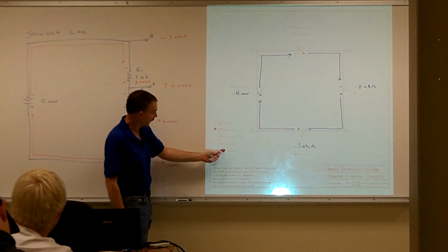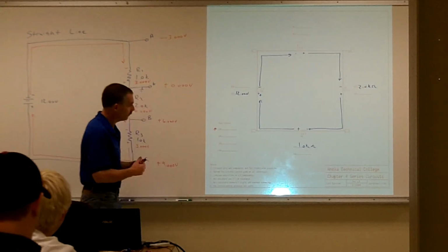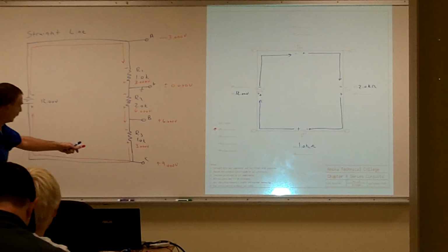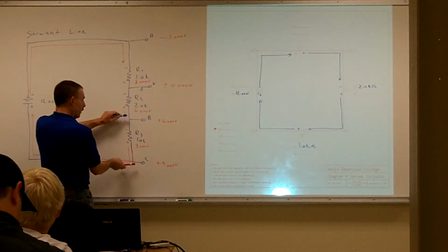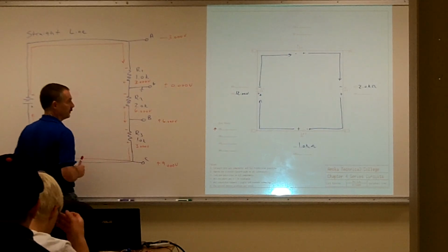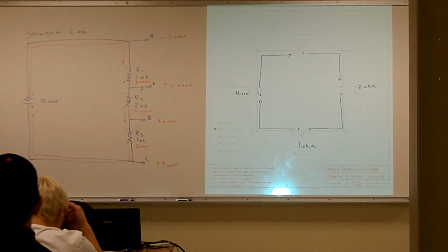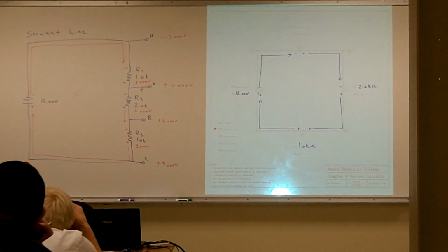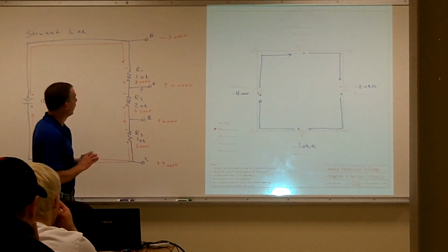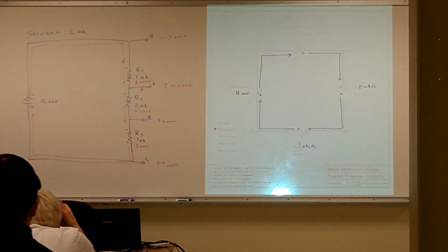But all test points require polarity, and voltage drops do not require anything. Because you can tell that it doesn't have anything to do with the voltage drop. It depends on where we're referencing our red and black leads. So no polarity on our voltage drops. All right, what would I get from B to A then?